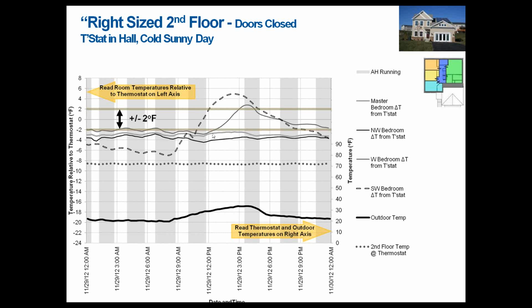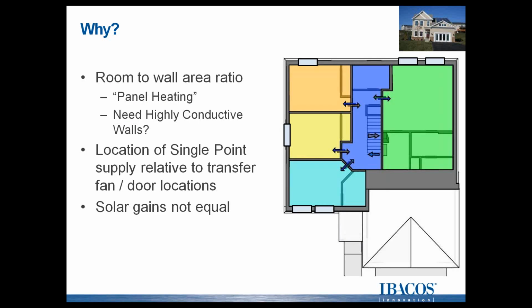And so some things that impact this are the conduction between different rooms. Potentially, if there were ways to improve the conduction between rooms, that could help mitigate this problem. A lot of the results were heavily impacted by the location of that supply register. And that single point of distribution, if it was blowing into one of these rooms, that room could potentially overheat or be undercooled while the other rooms were not. And the other most significant driver in this house was the impact of solar heat gain. So the front of the house faced due south. So the bedroom in the bottom corner saw the most significant impact of the solar heat gains, as well as this western bedroom. As we saw, those rooms tended to overheat when the rest of the house stayed comfortable.